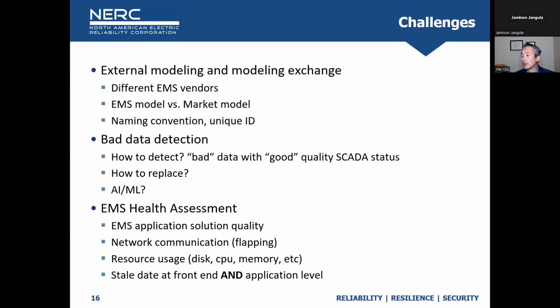Either one, so it depends. Also, the other challenge is the bad data with good quality SCADA status. If you're familiar with SCADA, you know it tells you good, bad, and also suspicious. Sometimes if you have a bad quality label on the measurement, it's very easy to detect what's going on. But for some breakers, they look very bad in the field. You know it's closed, but it tells you open. But the quality says good. So how do you trust them? Once you detect what's going on, how do you replace it with the right value? Maybe use AI or machine learning.